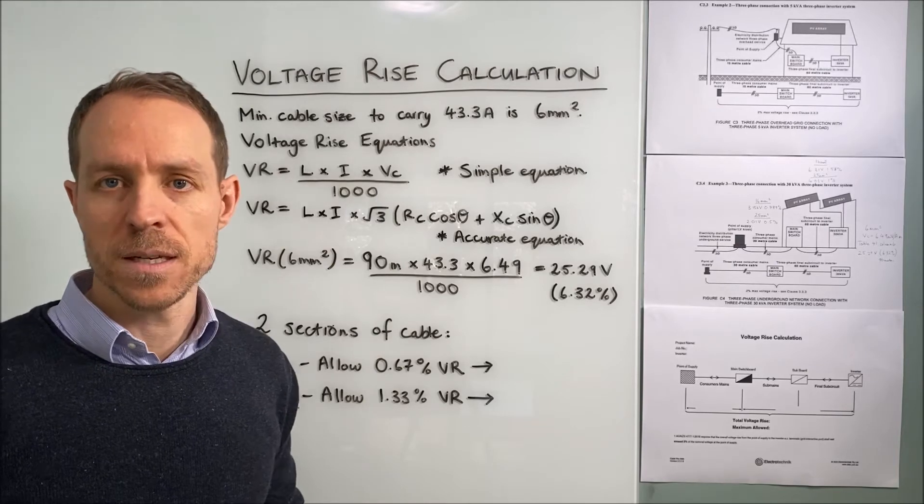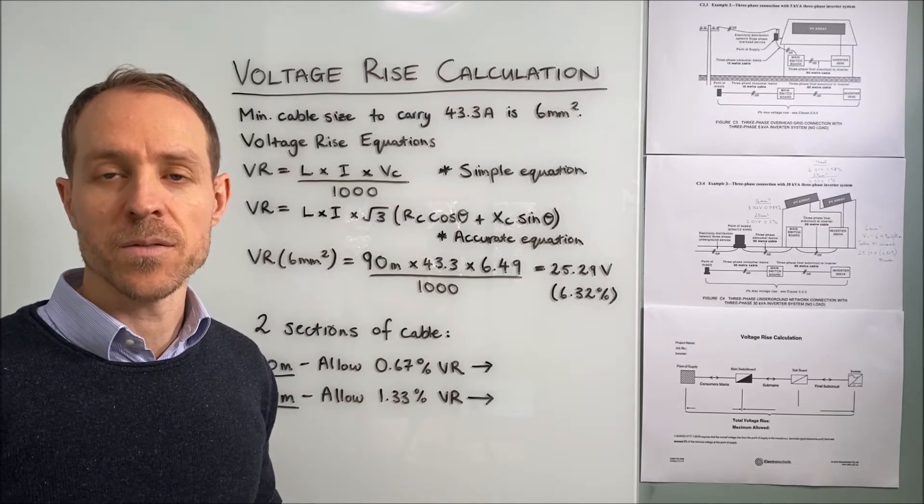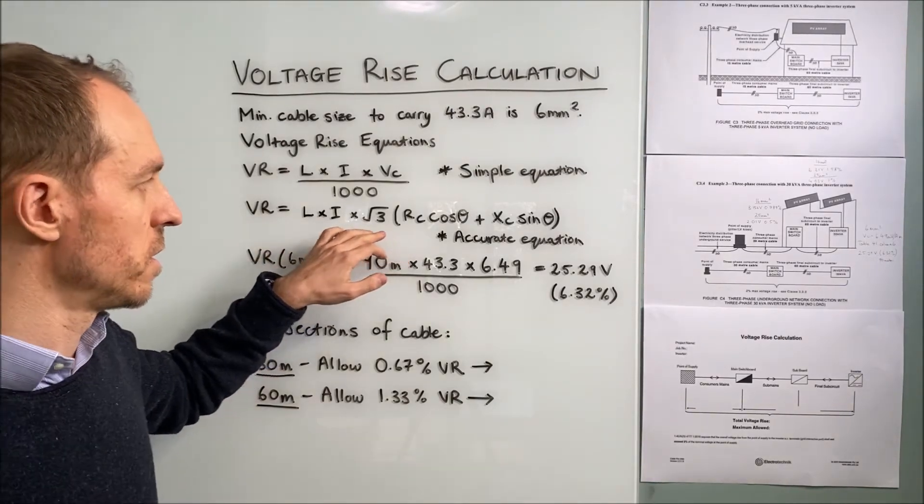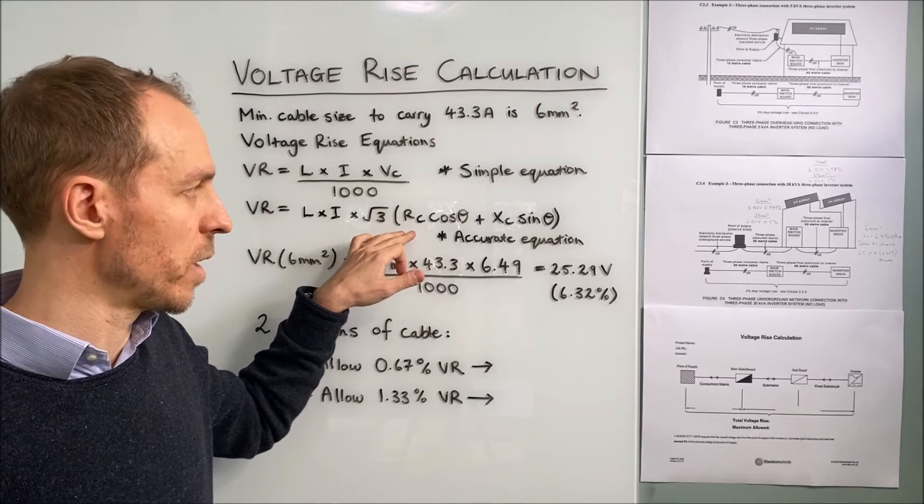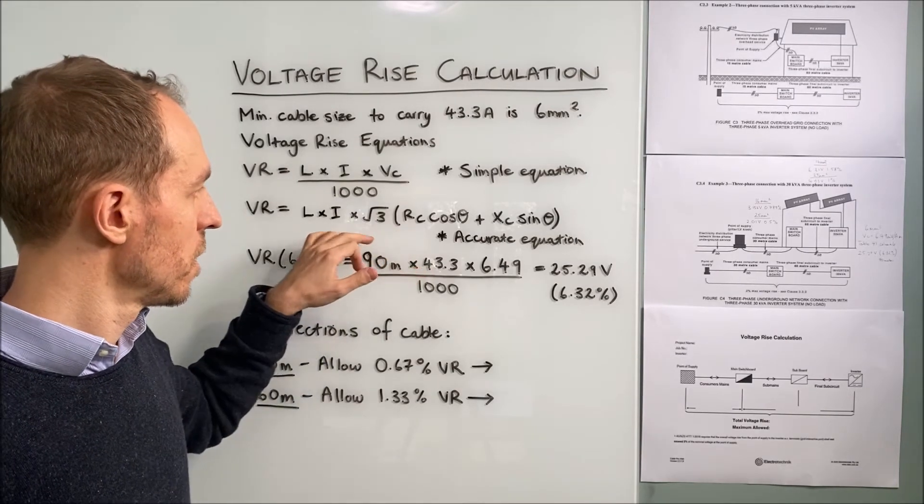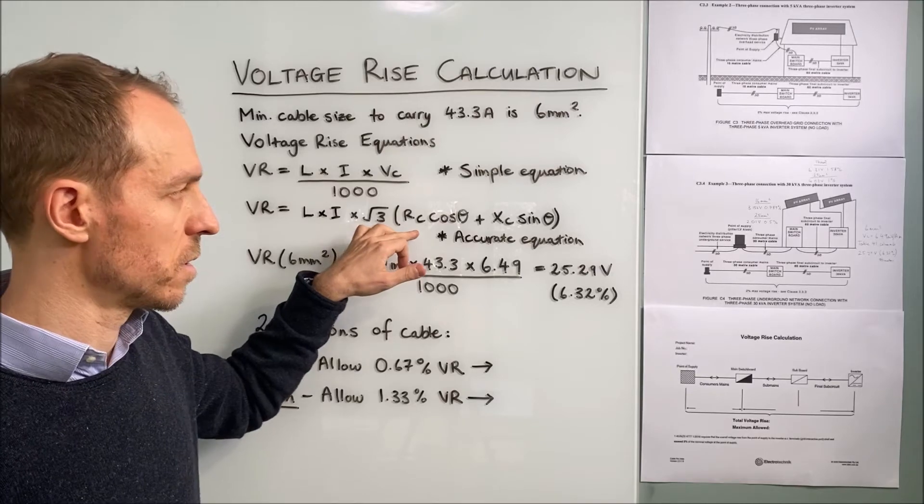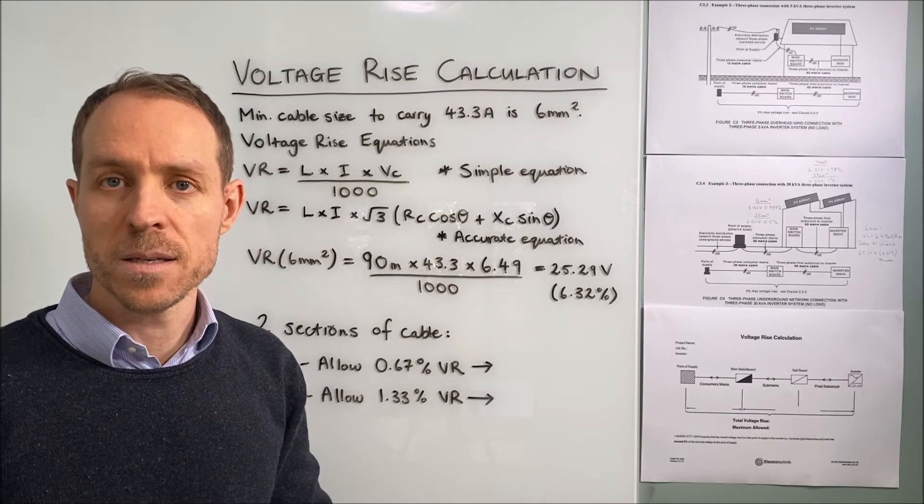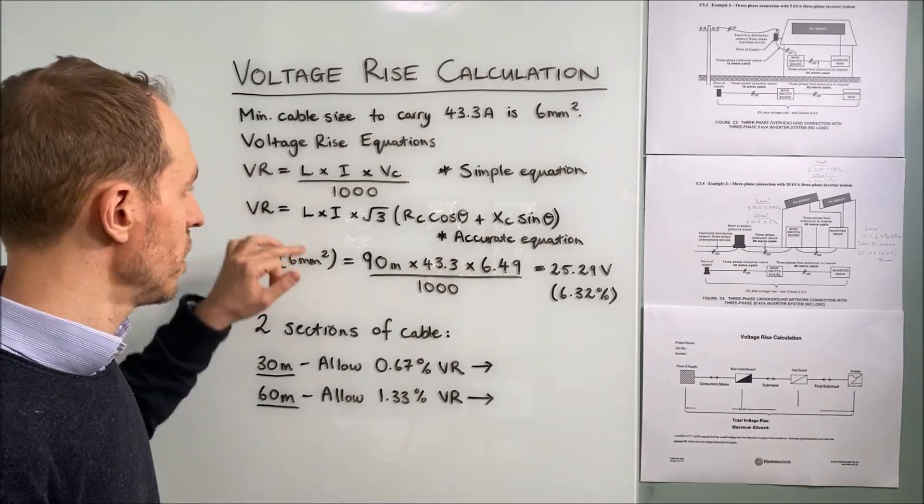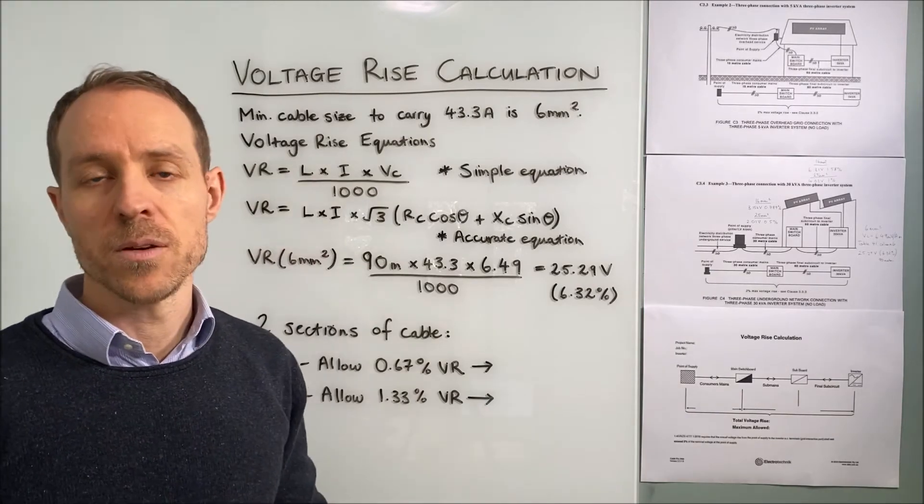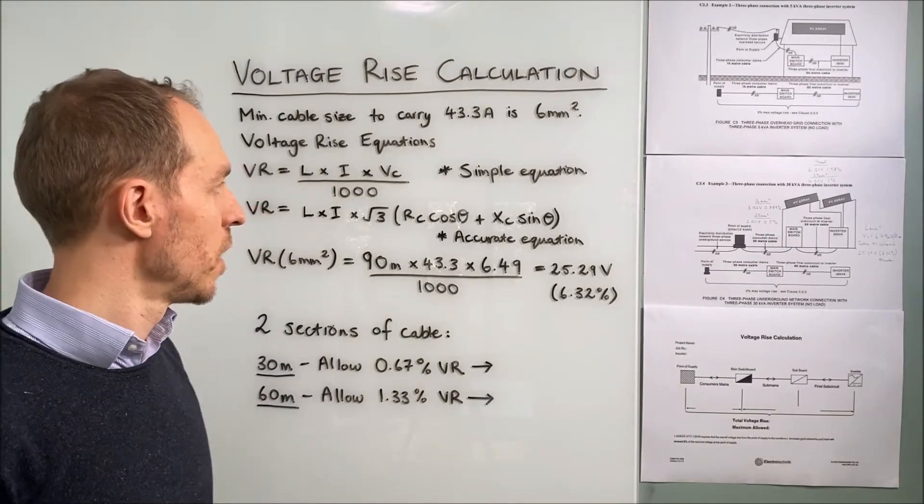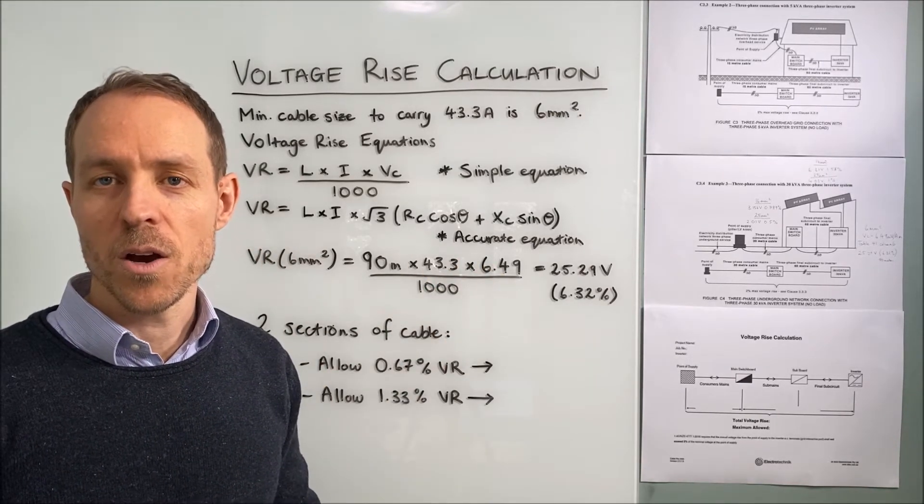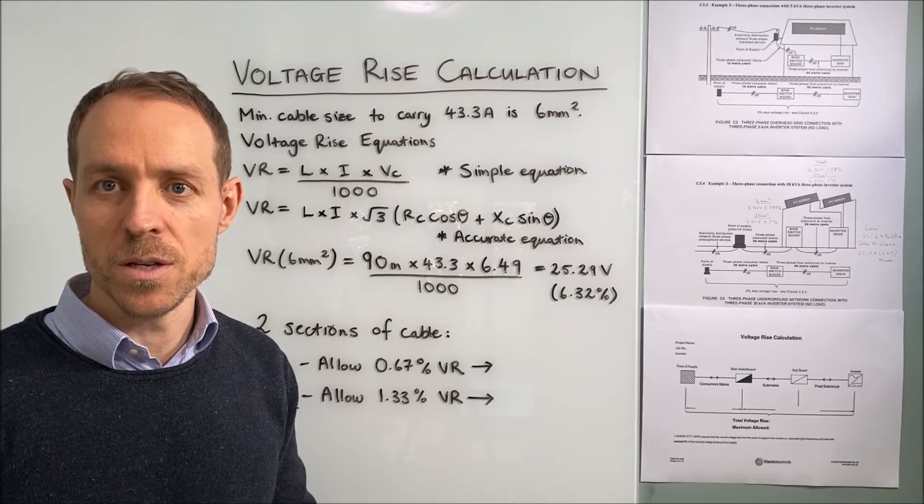The accurate equation which is the equation we're not going to use by hand but it's used by our software. This accurate equation uses cable resistance and reactance and considers power factor as well as cable operating temperature. Using this equation can result in smaller cable sizes. I should also mention you may have noticed that these equations for voltage rise are in fact identical to those for voltage drop.